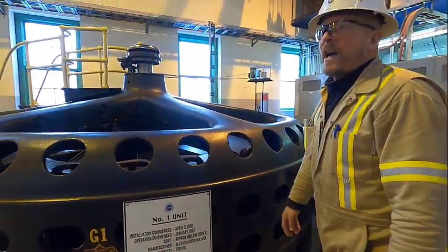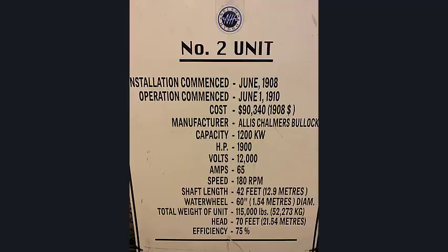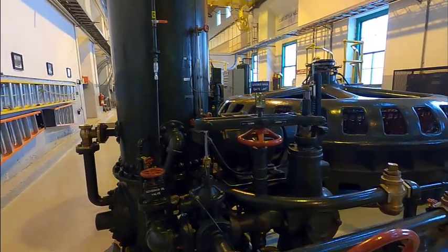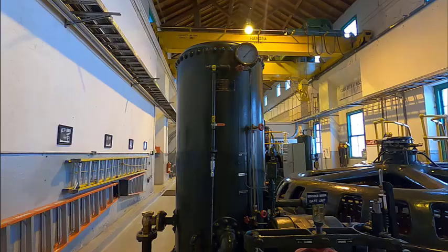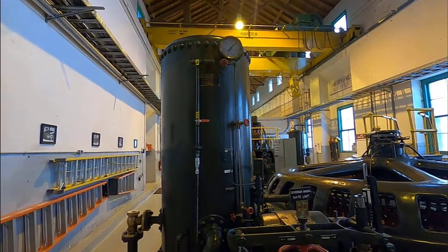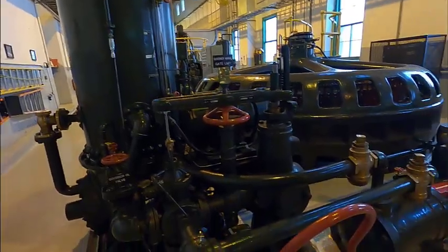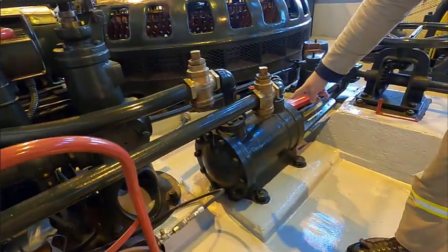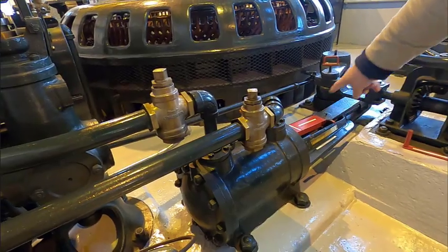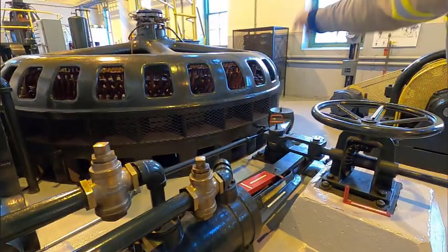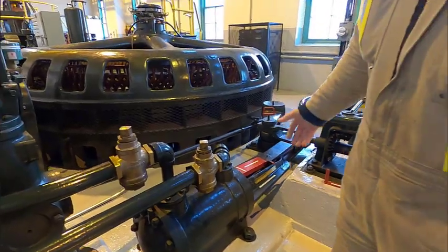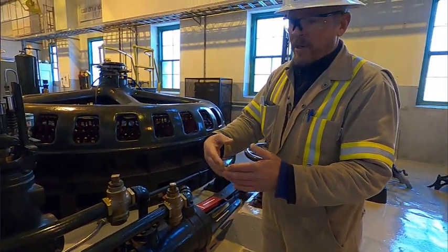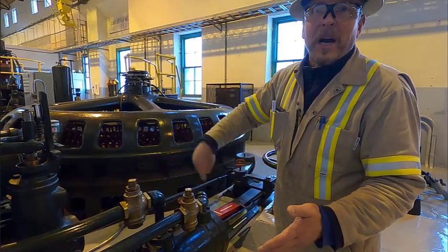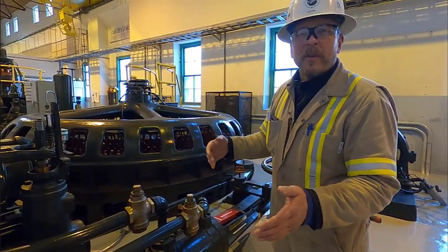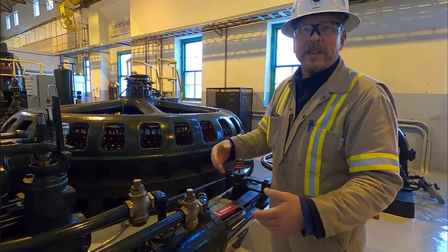So off to the side here, we'll go to our Unit 2. This is a hydraulic governor, so it's oil under pressure, about 200 psi. It operates a hydraulic cylinder, which is here, and by operating that hydraulic cylinder, it takes that movement force down to the turbine floor to operate what we call wicket gates. Wicket gates are like shutter doors that work simultaneously that surround the turbine, and that's what can stop the flow of water or start the flow of water to operate the unit.